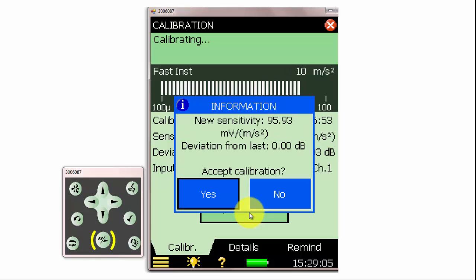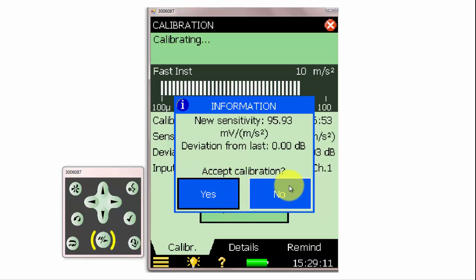After the meter has completed the measurement, we can click Yes to accept the calibration, or No to reject the calibration and perform it again.